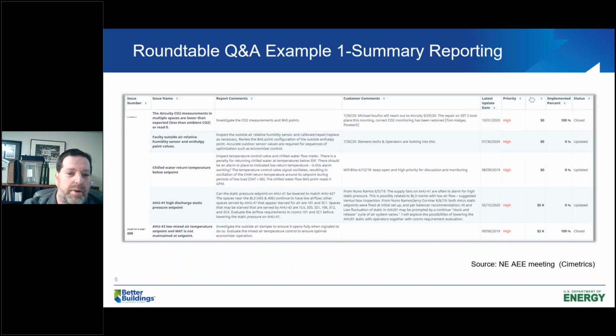Here's one example from an EMIS provider showing issue numbers assigned - this is one of their reports. There's a lot more information out there with all the EMIS providers, but you only necessarily want to look at a small amount at a time. This one assigns an issue number, names for the issues which could include a description of the problem, comments reported, and updates. Customer comments - if a customer is also working within your EMIS, there's interaction in terms of communication, which is very important. The latest update to the issue is also in the tracking with dates. There's a priority, so you could filter based on priority, the ones you want to address, savings, or status. For something like an economizer issue, you may not be able to see it during the winter time, so you may want to change the status to wait until next season, making it seasonal or something different. They can be sorted based on building, issue type, priority, and status.